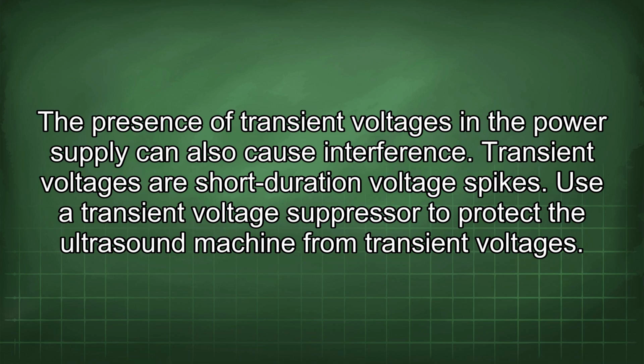The presence of transient voltages in the power supply can also cause interference. Transient voltages are short-duration voltage spikes. Use a transient voltage suppressor to protect the ultrasound machine from transient voltages.